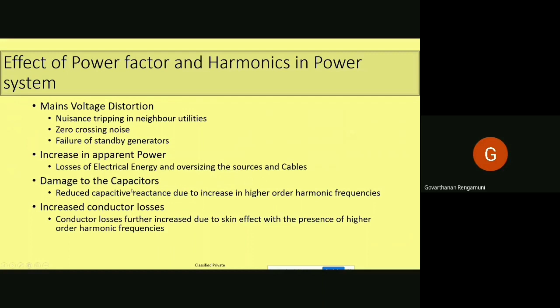The third one is damage to the power factor correction capacitors. Reduced capacitive reactance will happen because of the higher order harmonic frequencies. As you all know, the capacitive reactance will be lesser for the higher order harmonics. The fourth one is increased conductor losses. As you are injecting higher order harmonics, there will be a skin effect in the conductor. So the effective resistance will be increasing in the conductor, so the losses will also be more. So these are a few impacts because of the harmonic pollution.